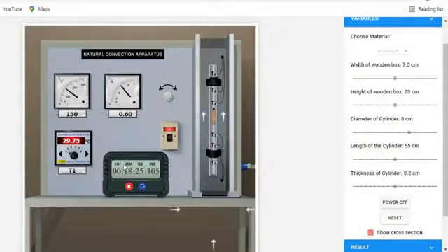Wait for 20 minutes, meaning for this particular watch. Once you see that all the numbers settle down, a steady state has come, and then again note down the temperatures. So T1 30, T2 148, T3 150, 154, 156. So as it is, the temperatures have not changed.